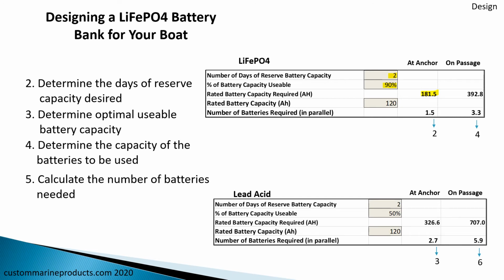So if we use a 120 amp hour battery, the system tells us that we need a battery and a half, or we round that up to 2 batteries. Under passage, we would need 4 batteries to go 2 days. If we look at lead acid, where we can only draw down 50% for the same 120 amp hour rated battery, we would need 3 batteries instead of 2. So we can use this worksheet and this methodology to compute how many batteries we need.